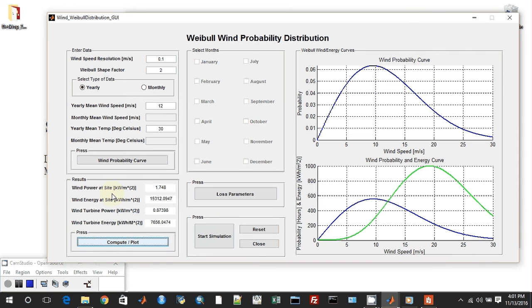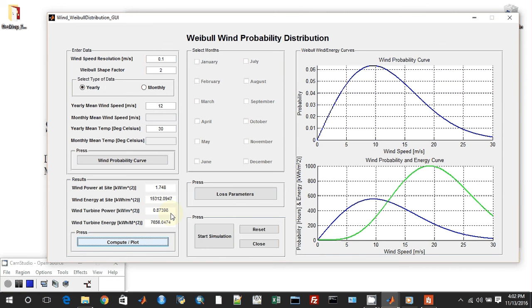This is the graph which we are looking at right now, and this is the same Rayleigh curve. It is the same curve over here, but now the x-axis for this curve is in hours. For this, the green graph represents the energy in kilowatt hour per meter square. For the blue graph, it represents probability in hours. Over here for both graphs, blue and green, this axis represents wind speed in meter per second. Some of the important results which we compute: the wind power at site per meter square in kilowatts is 1.748, the wind energy at site per meter square in kilowatt hours. All these values are per meter square because we don't know the area of the turbine. This is for the generalized turbine. The next result is the wind turbine power, which will be almost half of this because the CP which has been considered is 0.5, which is very much ideal. But it's okay to have an estimate value of some kind with us. This is the wind turbine energy which it can capture per meter square.